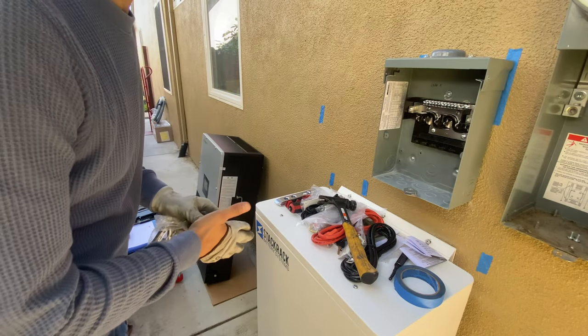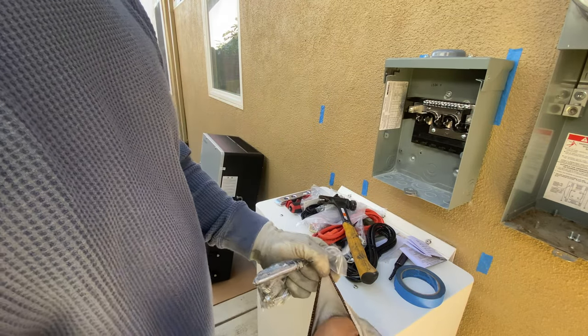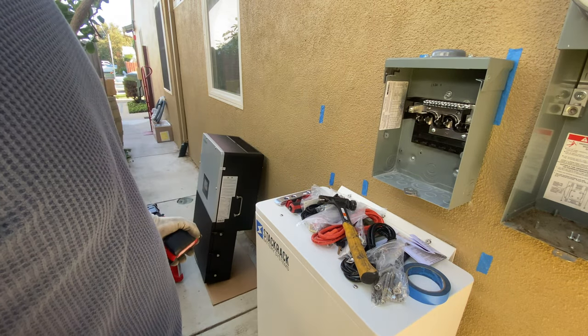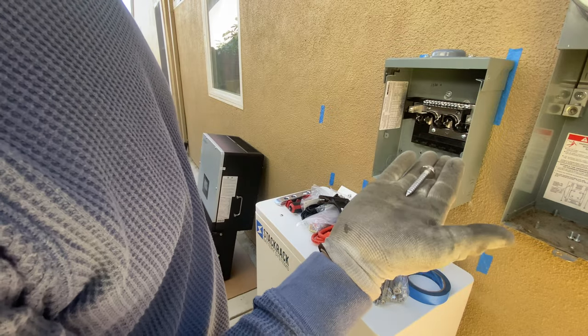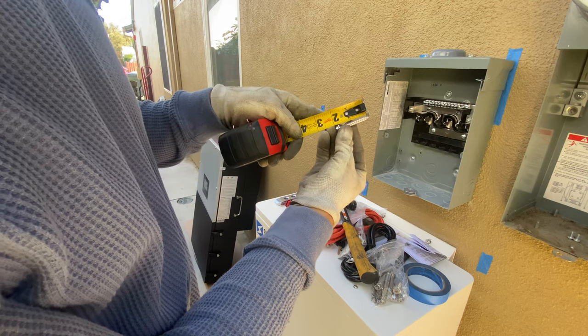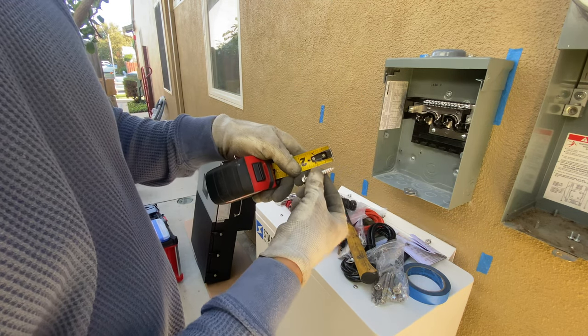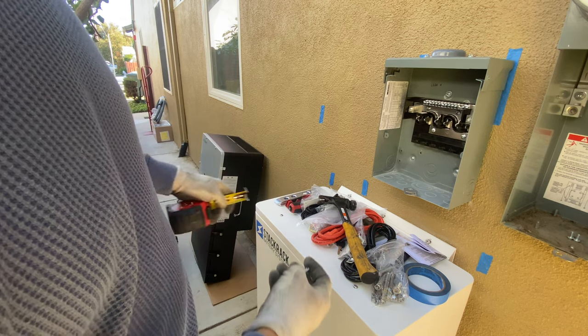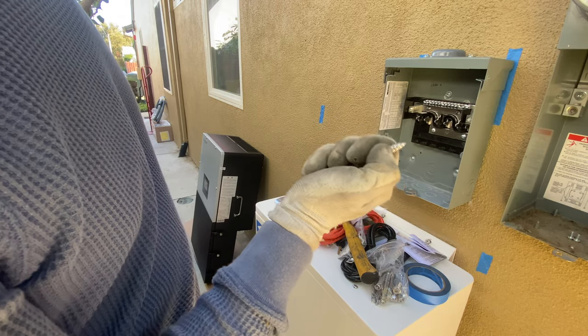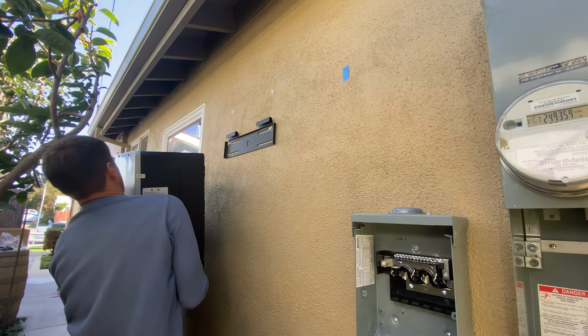In the package with the inverter, we are getting concrete anchor bolts which are three inches long, and that's definitely enough to hold the inverter weight. In this case we have a wood framing house with Stucco, and we're getting these lag bolts which are two inches long. The stucco is about one inch depth, so the embedment into wood is going to be about half an inch, which is definitely not enough — so we have to get our own lag bolts to hang the inverter.